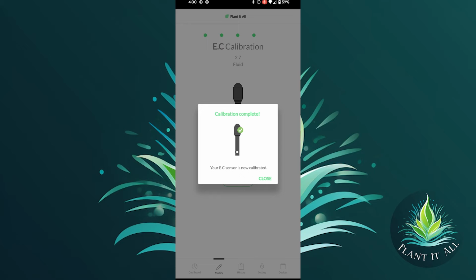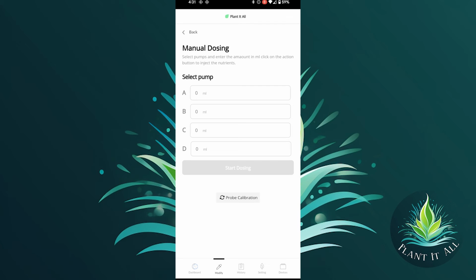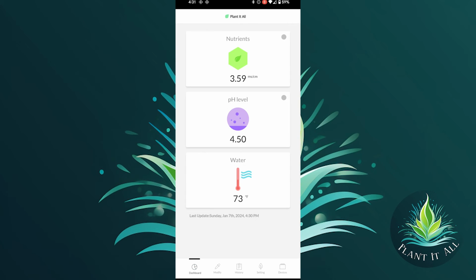Okay, we're done. Go ahead and hit the close button on the card there. And now we can go back and re-enable all of our automations. So you can see all the values look weird. It's okay. It's going to take care of itself in just a moment. Once you go into each of the cards and reinitialize your settings, you are going to be all set. The Growee is going to take back over, and now you've got your freshly calibrated EC probe.